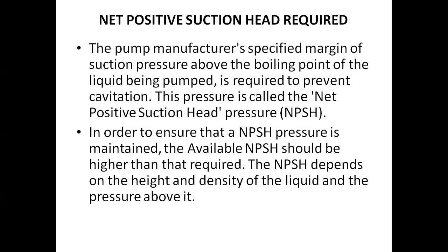The net positive suction head required is the pump manufacturer specified margin of the suction pressure above the boiling point of the liquid being pumped, required to prevent cavitation.